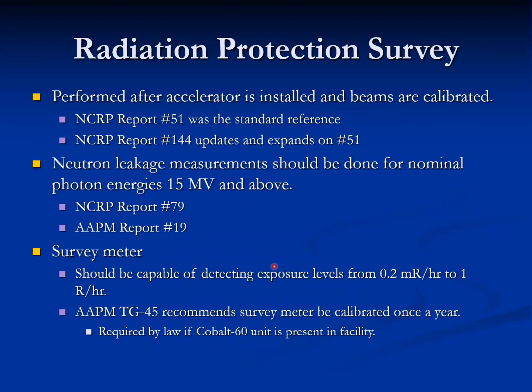Perform a radiation survey before starting the machine. This will also include neutron leakage measurements, which should be done for nominal photon energies of 15 MV or above. The survey meter should be capable of detecting exposure levels from 0.2 mR per hour to 1 R per hour, and you can follow the relevant reports.